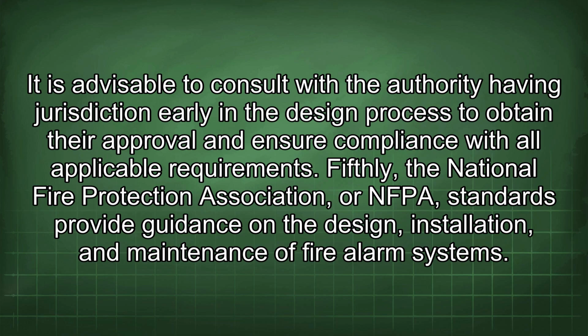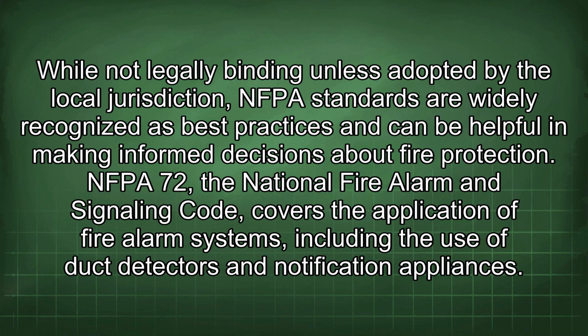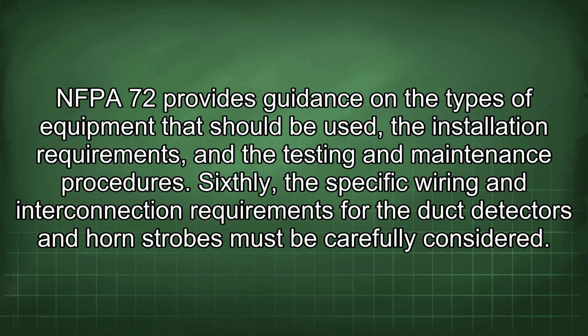Fifthly, the National Fire Protection Association, or NFPA, standards provide guidance on the design, installation, and maintenance of fire alarm systems. While not legally binding unless adopted by the local jurisdiction, NFPA standards are widely recognized as best practices and can be helpful in making informed decisions about fire protection. NFPA 72, the National Fire Alarm and Signaling Code, covers the application of fire alarm systems, including the use of duct detectors and notification appliances. NFPA 72 provides guidance on the types of equipment that should be used, the installation requirements, and the testing and maintenance procedures.